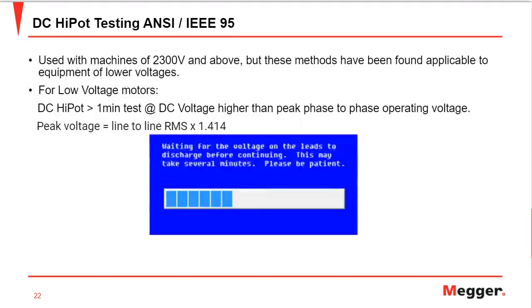Also, whenever the test is done, it's very necessary to discharge the energy. So the HiPot tester does that. It discharges all the energy. Once the test is done, it discharges the energy through the ground.